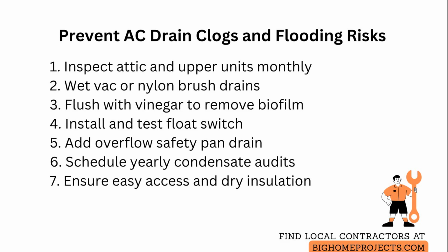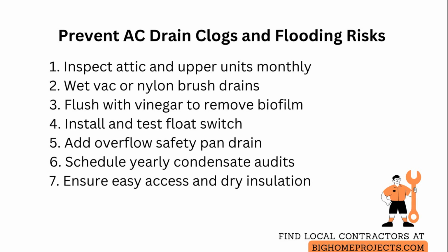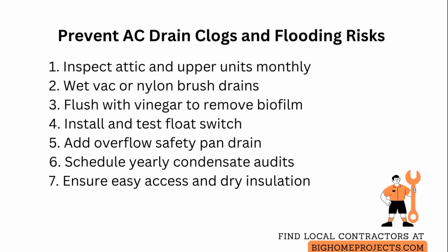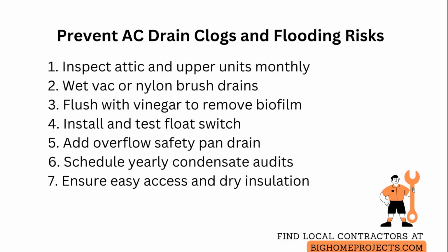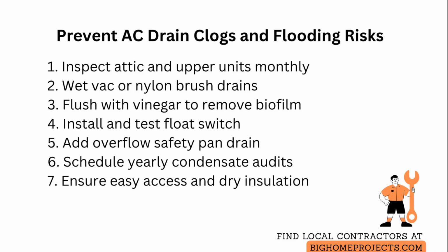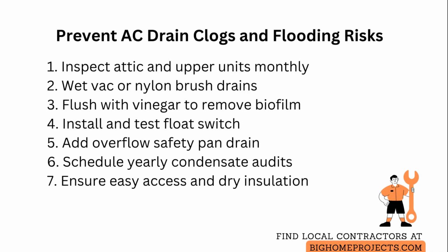For long runs or hard-to-reach units, schedule professional condensate audits yearly and ask technicians to camera inspect long sections of drain line to find sags, pinches, or degraded joints where clogs form. Keep attic insulation and plenums dry and allow easy access to the indoor unit, because prompt detection and repair prevents mold growth that can spread through ducts and cavities.